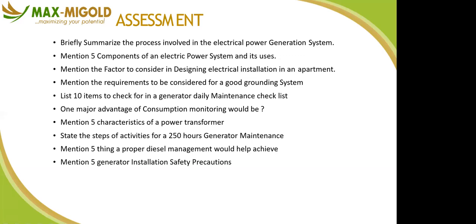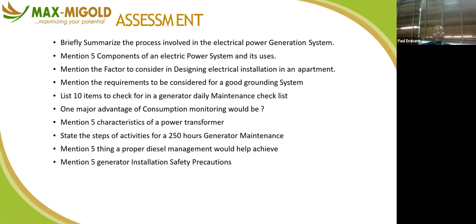Yes. If you have a trend of the load demand, that's why I mentioned peak and off-peak periods. With the way they are using it, you know how much load, how much current, or how much energy they actually consume. You understand? So you can as well dispose of those. We can keep that 200 kVA or 250 kVA and go for a lesser one. When you feel they are loading to full capacity, you go according to how they are loading. So if they are reducing, you go with a lower capacity generator. And the cost of running diesel also goes in that proportion.